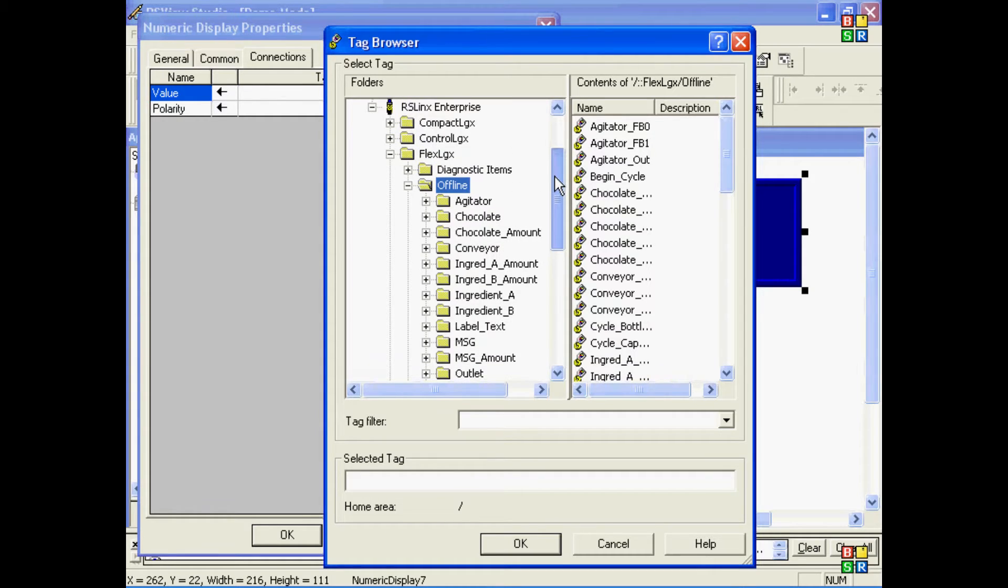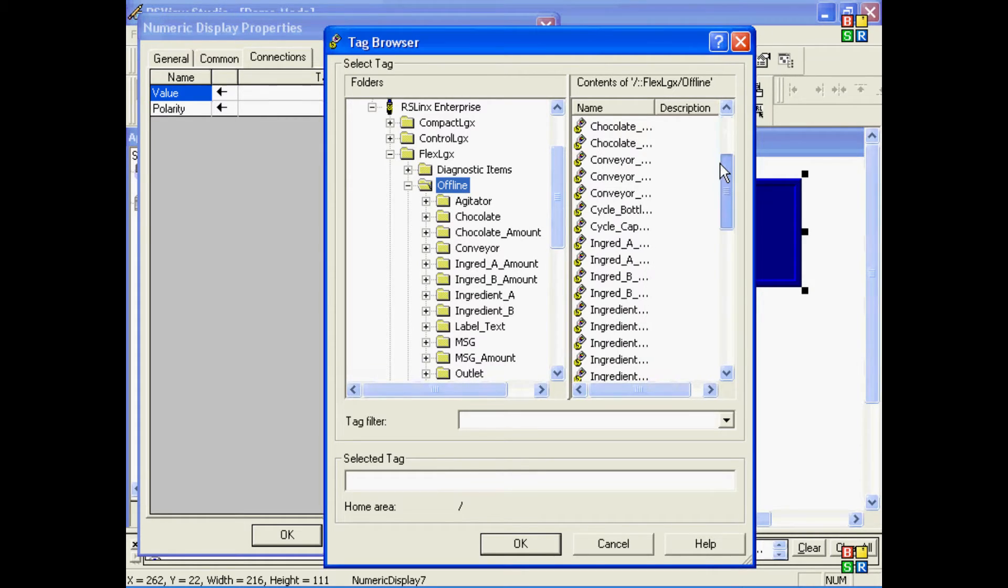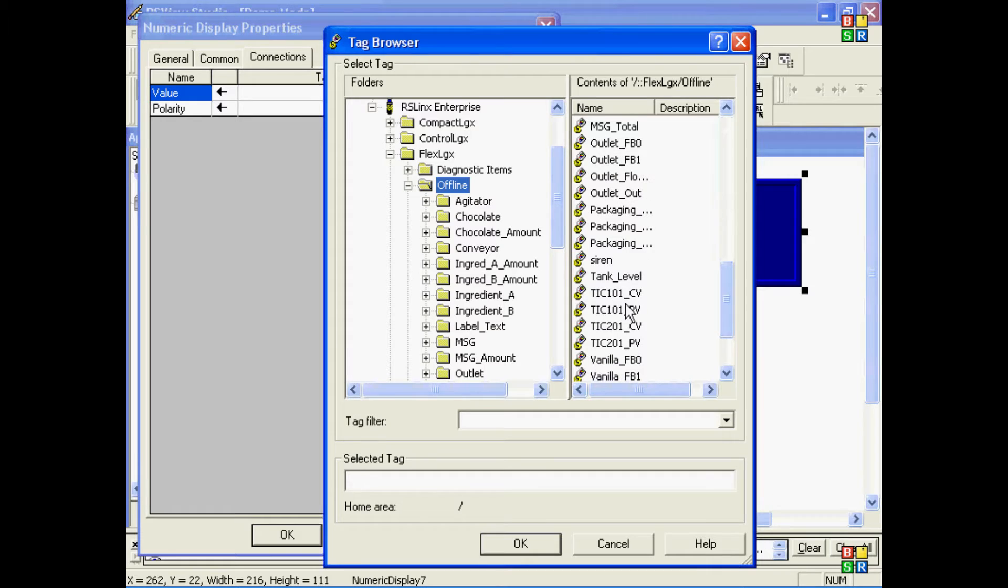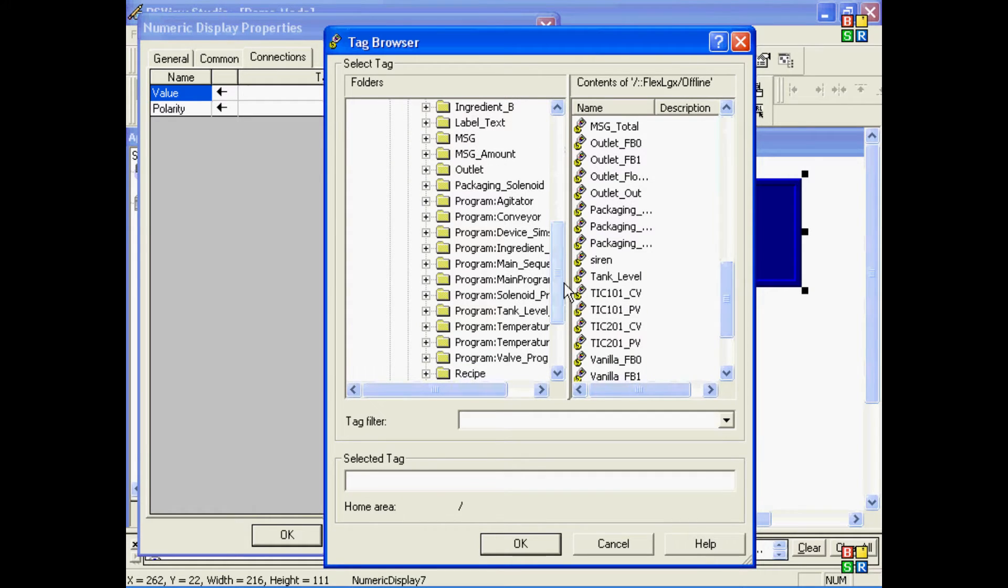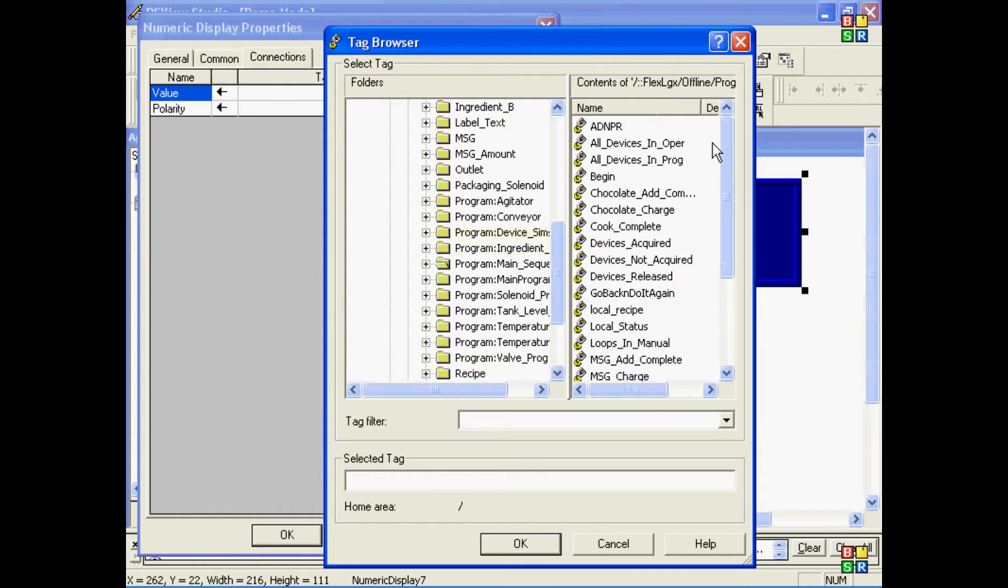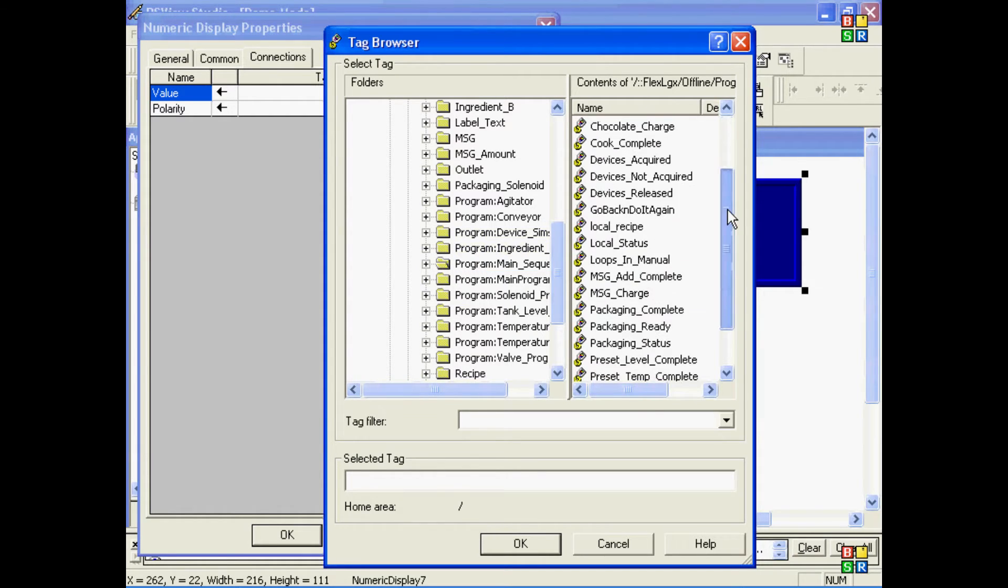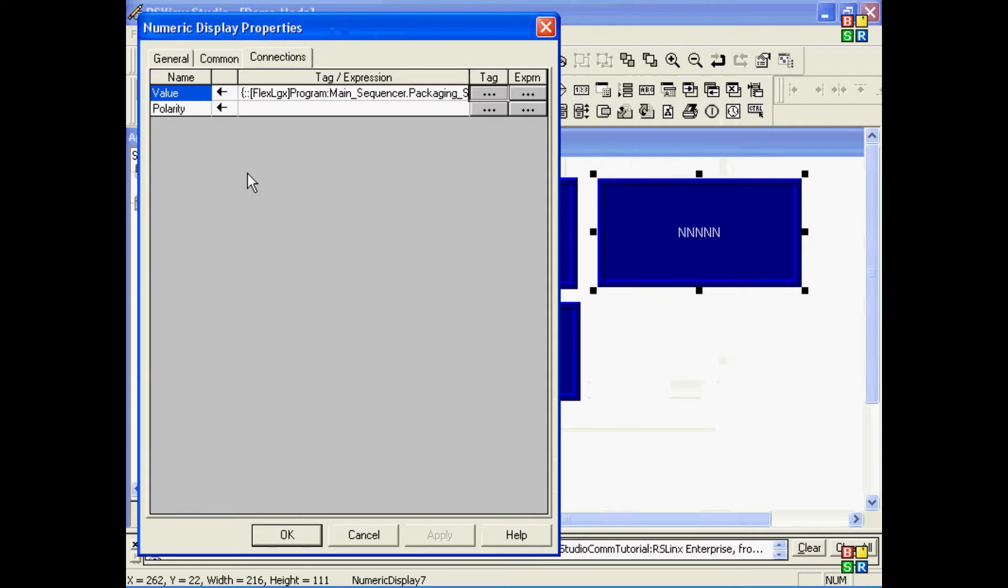Now, again, when I choose the Offline Folder and it opens, I can see all the objects, or what we call the controller tags. And again, I can go into a Program Folder and see Program Tags. In this case, I'll go ahead and choose one of these tags. Again, the shortcut name is part of the reference, so you do not want to change your RSLinx shortcut name after you've chosen tags for your objects on your screens.